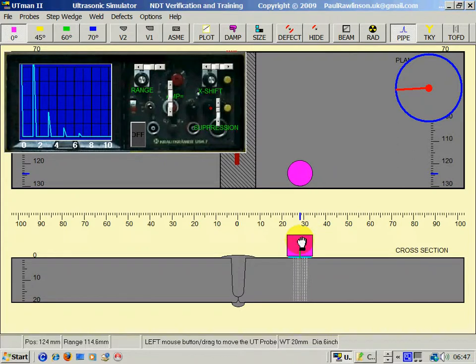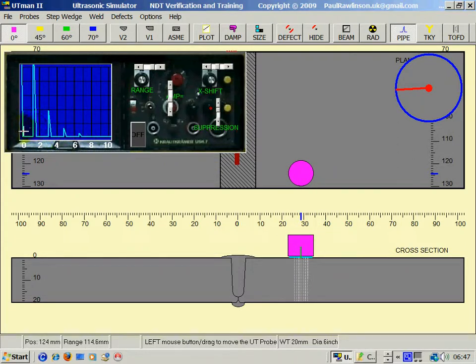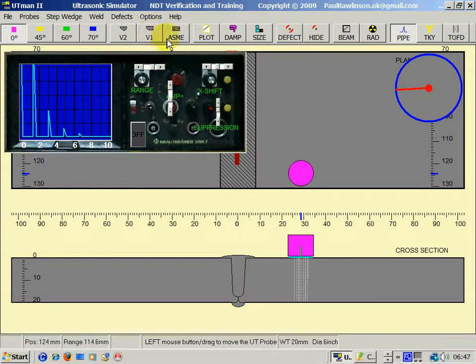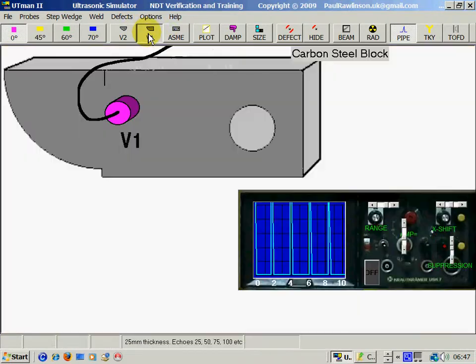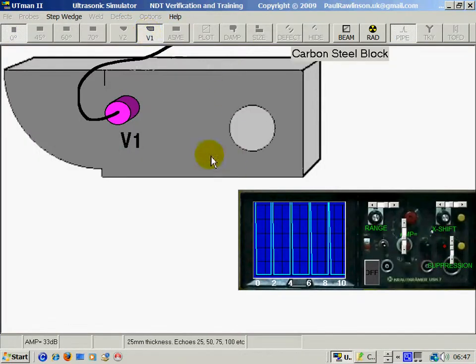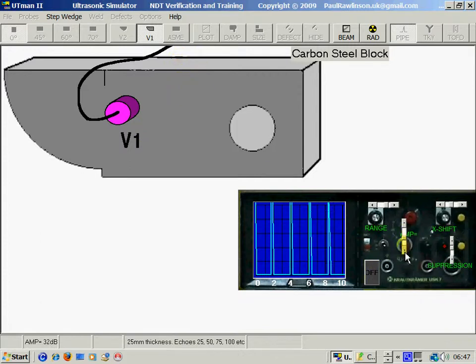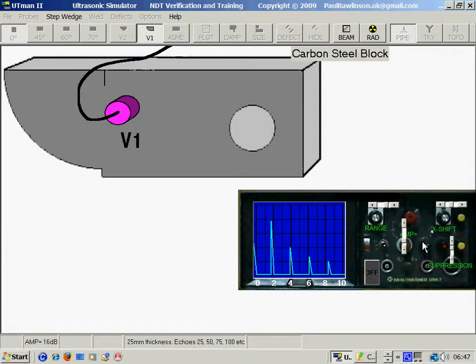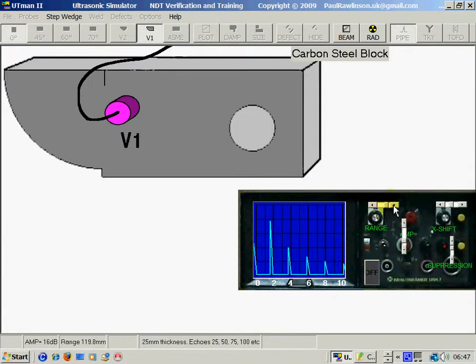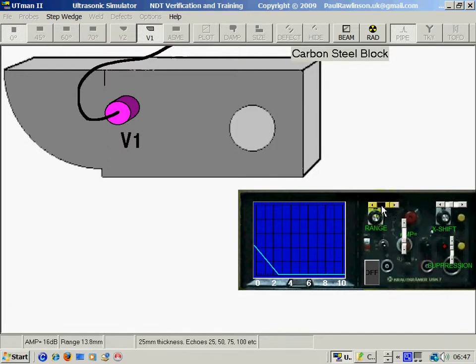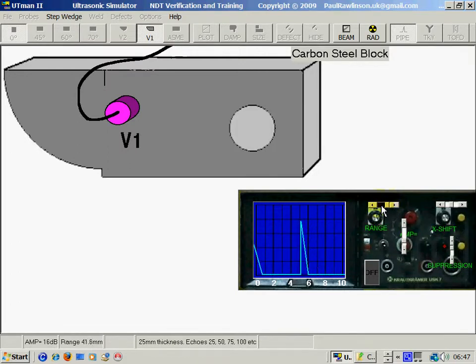Now to make sense of the UT set we have to calibrate the distance from left to right. For this we use a standard calibration block called a V1 which is 25mm thick, giving multiple 25mm echoes. I will set two of these echoes on the screen to give a range of 50mm.